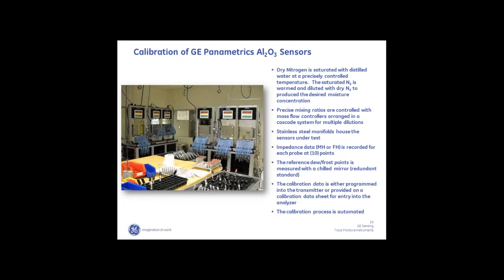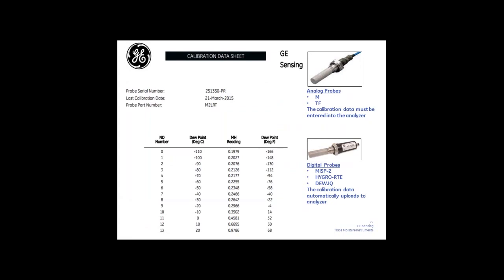As a customer, you have access to your calibration data online at any time — just register, enter the serial number, and download the calibration data for your probe. We have five of these calibration banks in our facility in Boston, as well as banks in Shannon Ireland and other countries including Japan, China, Australia, the Middle East, and South America. When you receive a probe, you're given a table of MH — our nomenclature for the impedance value — versus dew point. For an analog probe, you enter this 14-point table into the analyzer; for a digital probe, the data is automatically uploaded when you plug the probe in. If you send a probe back for calibration and it's analog, you'll need to enter the new data when it returns.